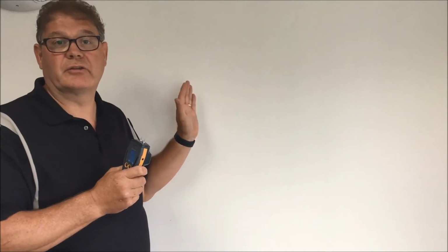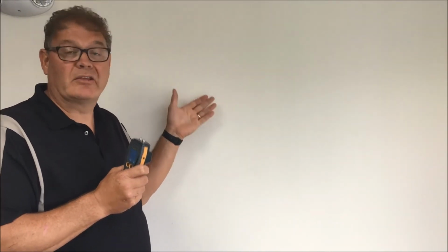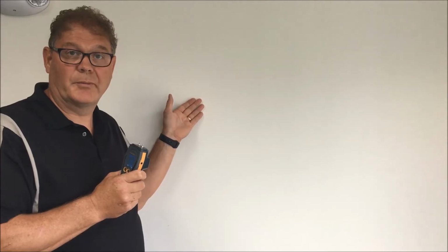So the Surveymaster has two modes of operation: a pin mode, which is essentially a surface or just subsurface measurement mode, and this non-invasive mode. The non-invasive mode by Protimeter will give you an average across its depth of measurement as a reading, whereas some just will give you the highest reading. So often you can use non-invasive measurement and it'll give you a full-scale defective reading, which means you may think that the moisture is soaked throughout the wall.